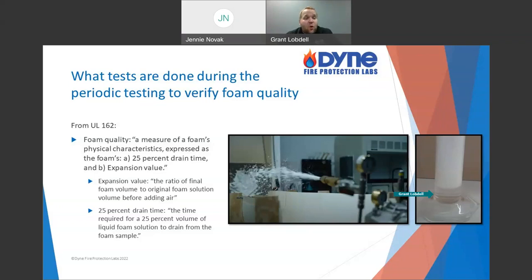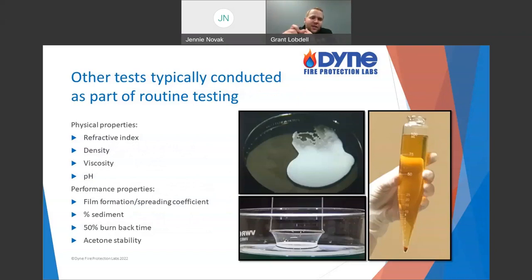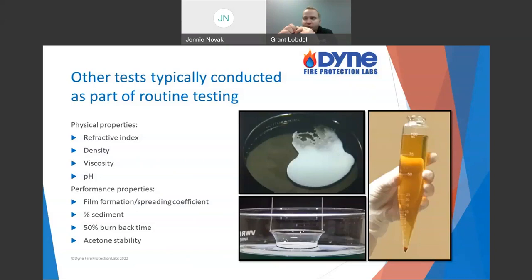What tests are done during the periodic foam quality check? Expansion and drain time are really the big ones — you can do those on every foam concentrate. But there are certainly other tests as well. We talked about expansion and drain time being the performance-wise foam quality essentials. There's a third one just as important: film formation, or the spreading coefficient.